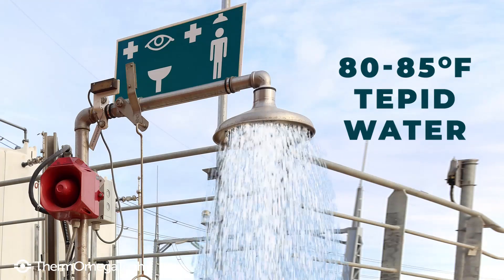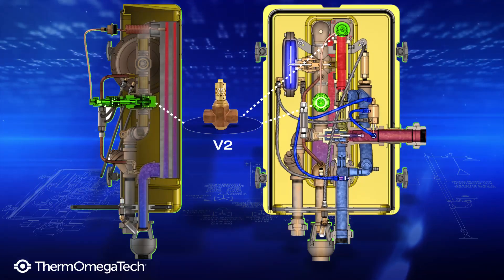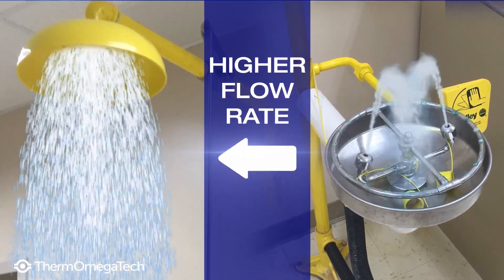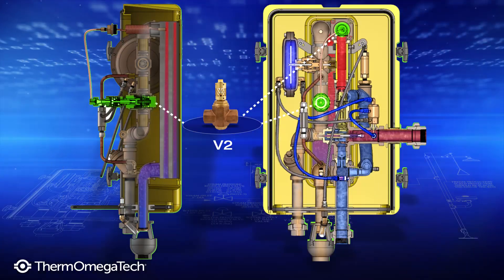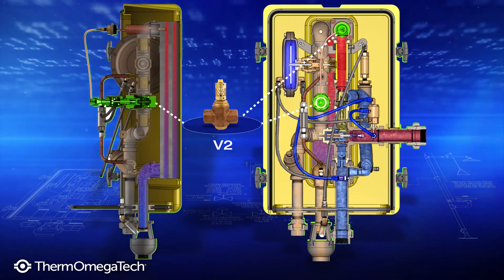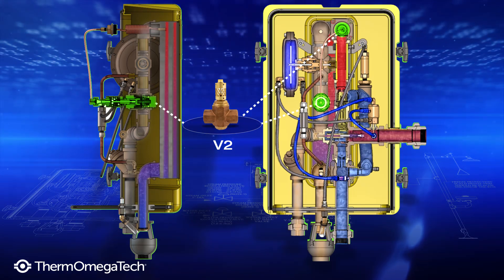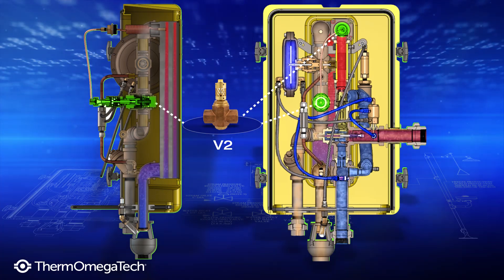Hot water exiting the heat exchanger passes by the V2 temperature sensor. When the safety shower is activated, there will be a higher water flow rate than when the eyewash is activated. To accurately proportion the amount of steam needed to heat each amount of water, V2 monitors the water temperature via the bulb and capillary and adjusts the amount of steam entering the heat exchanger, thus controlling the water temperature exiting the exchanger.